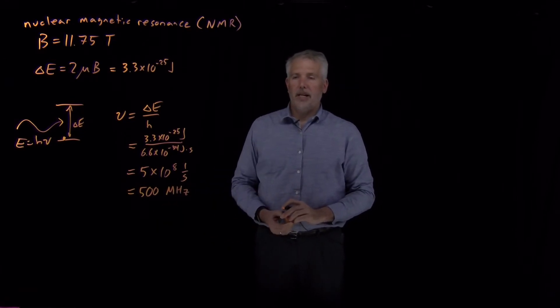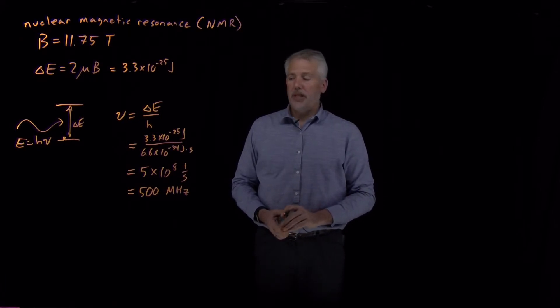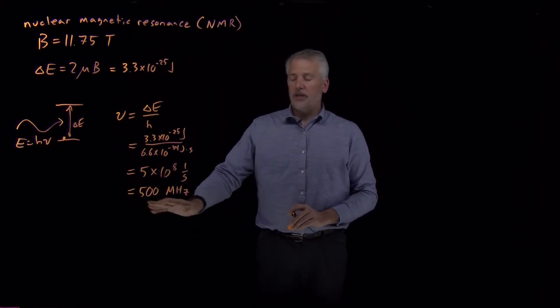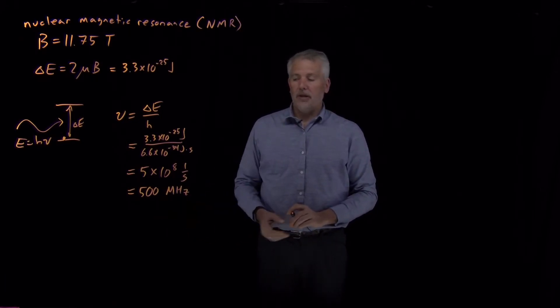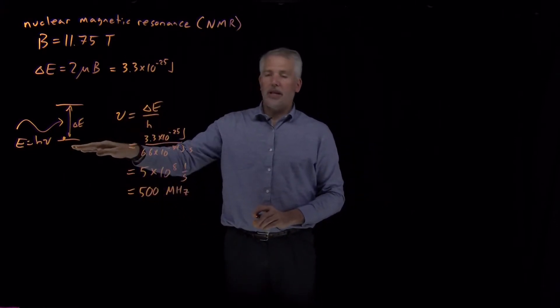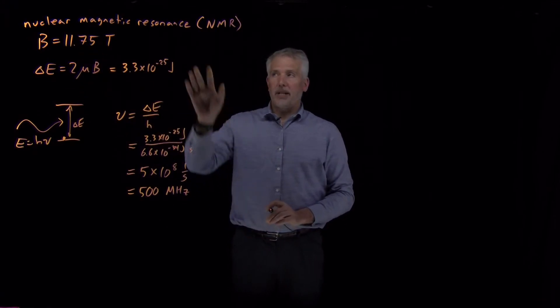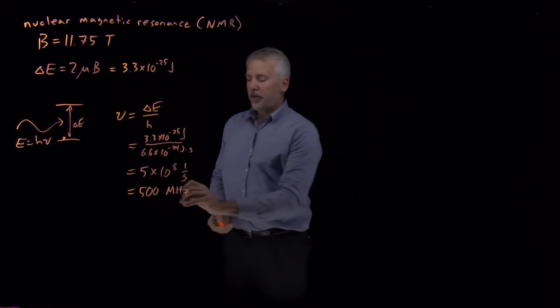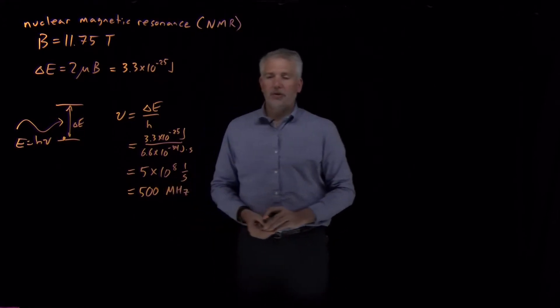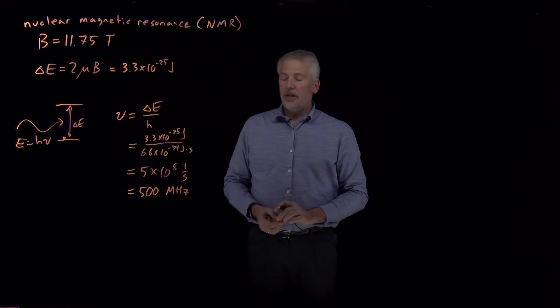Converting to hertz, that's 500 times 10 to the 6th hertz, or 500 megahertz. So when we say a particular NMR instrument is a 500 megahertz NMR machine, that means photons of frequency 500 megahertz have the proper energy to excite protons in the magnetic field of the magnet inside that NMR. 500 megahertz is fairly typical for a typical-strength magnet in an NMR instrument.